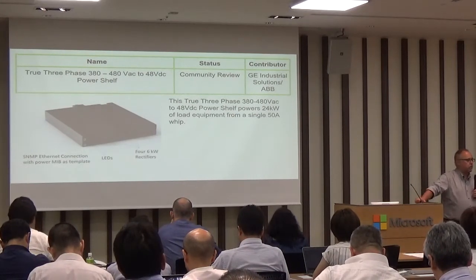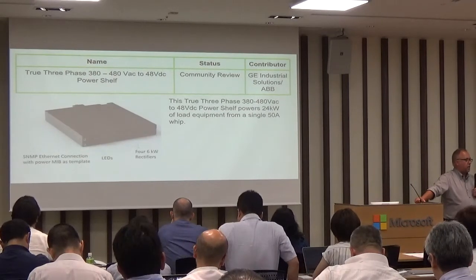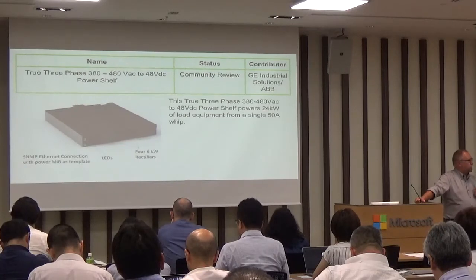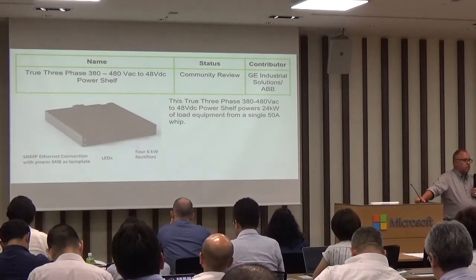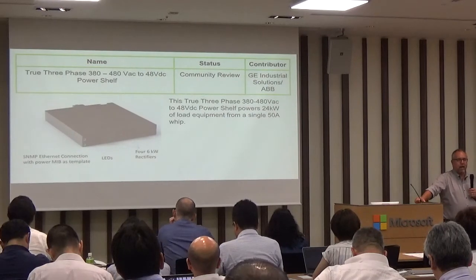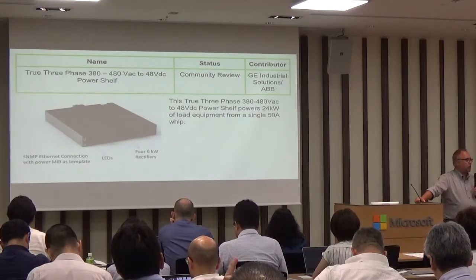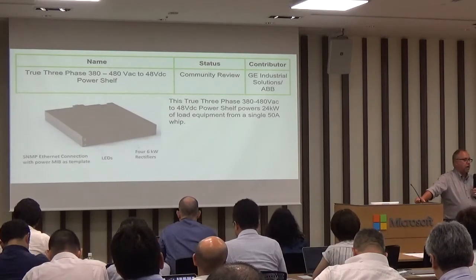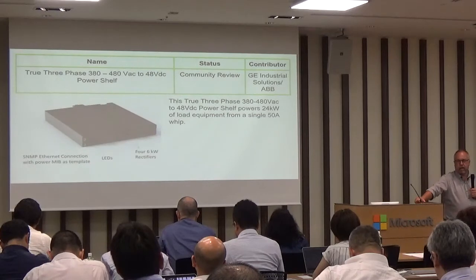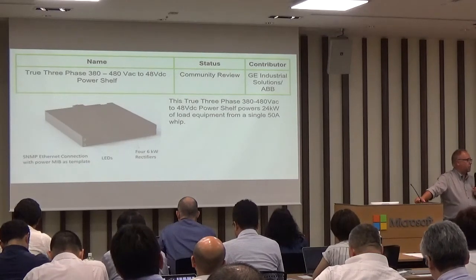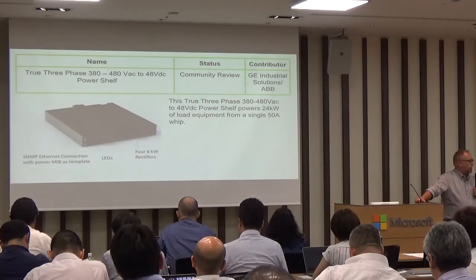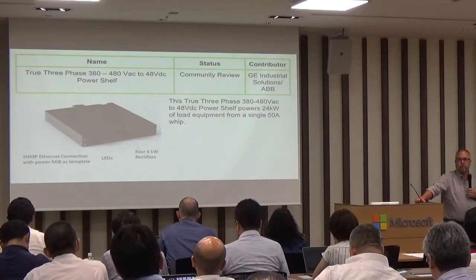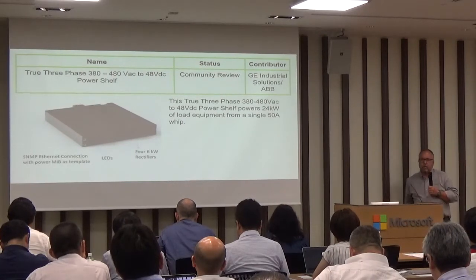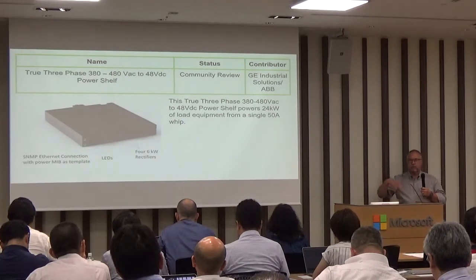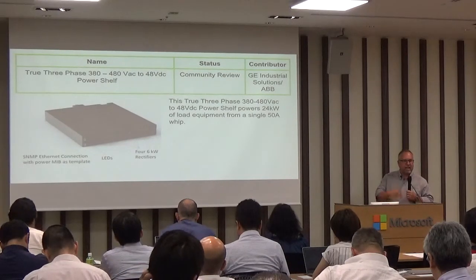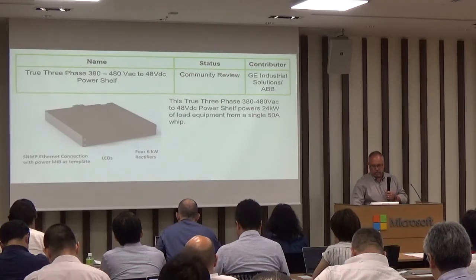We don't see a lot of usage today for 48 volt, but we believe 48 volt will see more and more adoption as rack power exceeds 25 kilowatts, or exceeds 50 kilowatts. We have customers actually building racks today that draw 75 kilowatts of power, and in those configurations, it's actually better to run the bus bar at 48 volts. So here's an example of how this community is enabling that change and that innovation down the road.